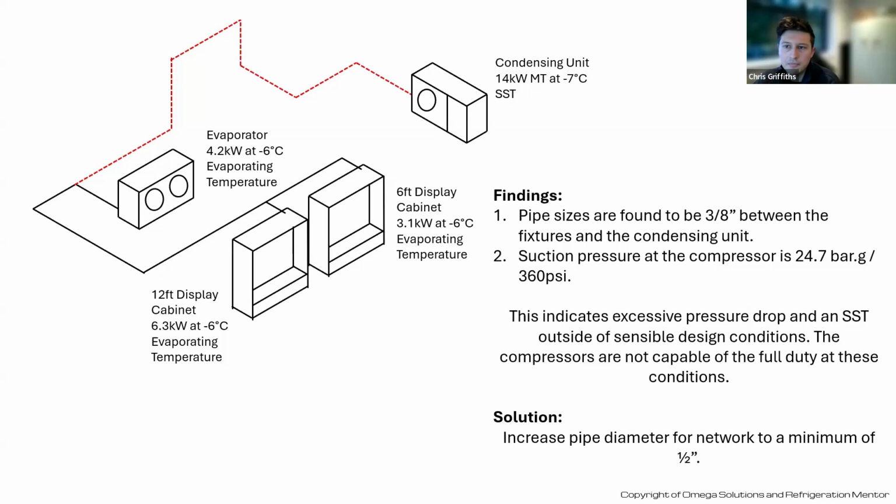A good rule of thumb, the bare minimum I would say, is a 2 Kelvin pressure drop, which is 3.6 Fahrenheit. That should be the most pressure drop you really get, because at that point you're throwing money away in terms of reducing the efficiency of your compressors. But if you design around half of that value or 75% of it, and don't factor in any of your bends or fittings, which do actually occur in real life, you haven't had to model them, but you can be fairly confident it won't drop below what your actual saturated suction temperature needs to be.